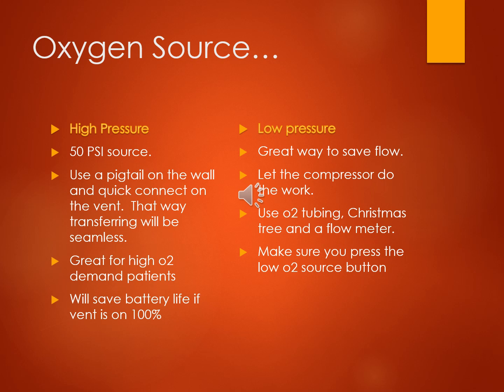They have a 50 psi connect on the outside. You can screw one of those pigtails into that and then run a quick connect off of that tank so you can plug the vent in really quickly. There's no lapse in O2 delivery. Those are really good for high O2 sources. If you want to do 100%, that's how you would deliver 100%, off your 50 psi source. Just remember that too, when you're at a high FiO2 and you're running that with the 50 psi going through there, you're going to save battery life.